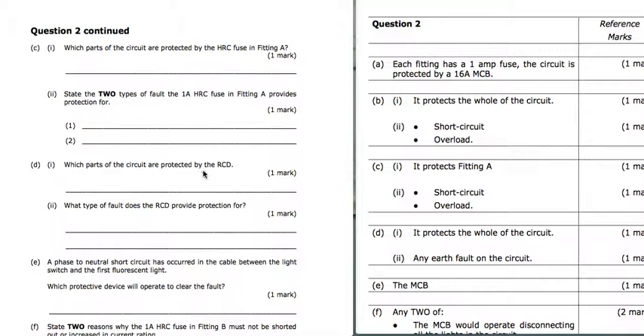Which parts of the circuit are protected by the RCD? So it protects the whole of the circuit. What type of fault does the RCD provide protection for? So it provides an earth fault on the circuit. So it won't provide protection for short circuit or overload, only for earth leakage faults.